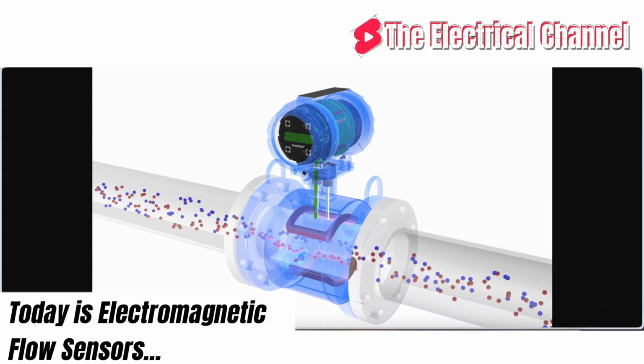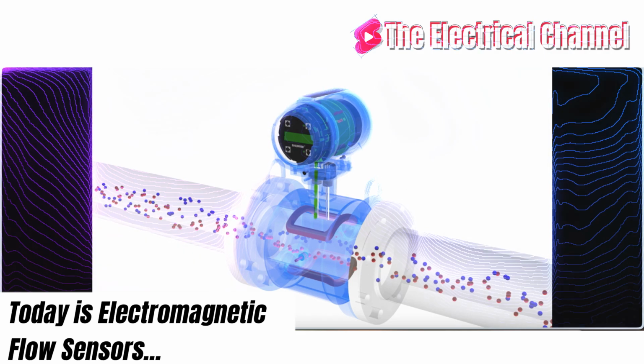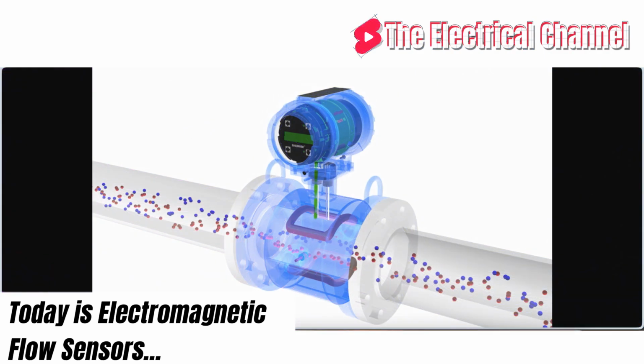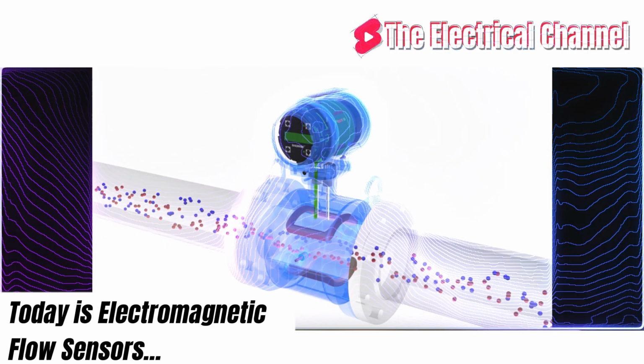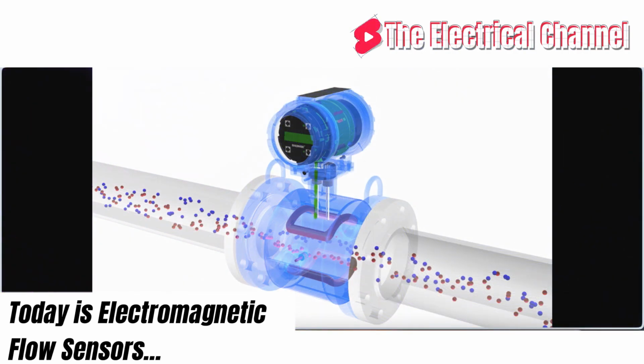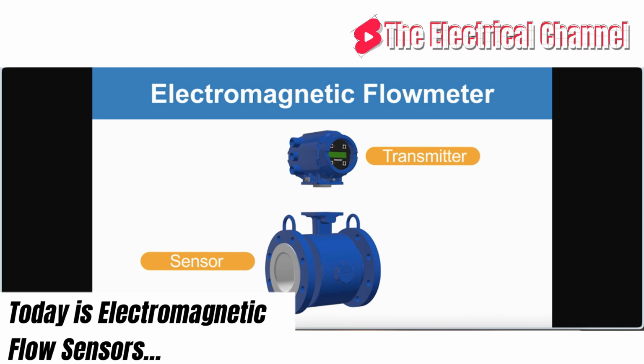Most sensors convert the flow into process output signals of 4 through 20 milliamps, or 0 through 10 volts DC, or 0 through 5 volts DC, pulse or frequency. A switch output can often be added to control external equipment based on a flow set point.